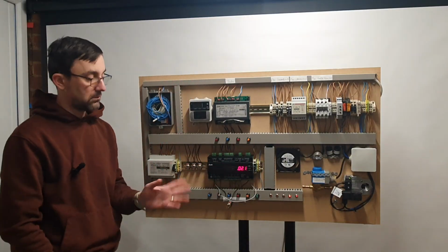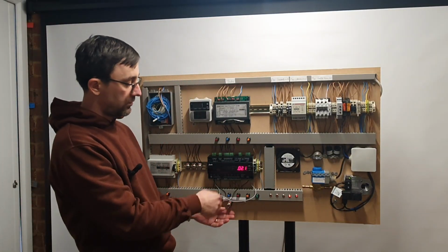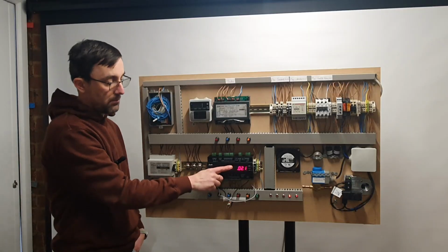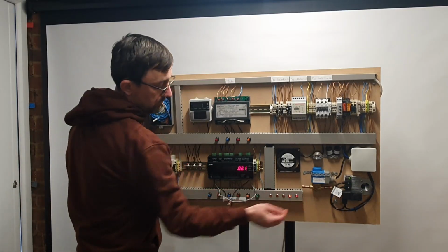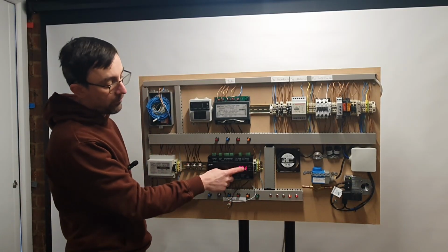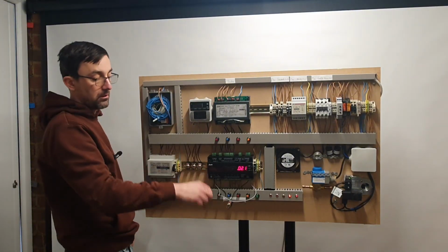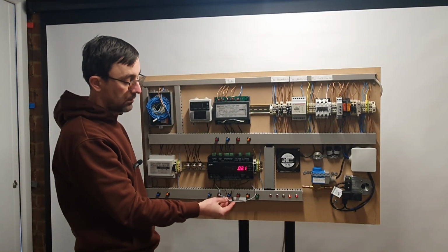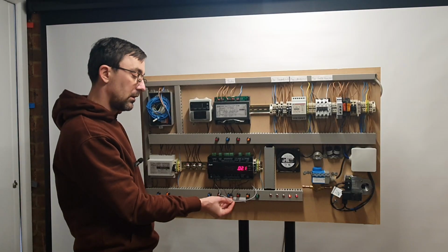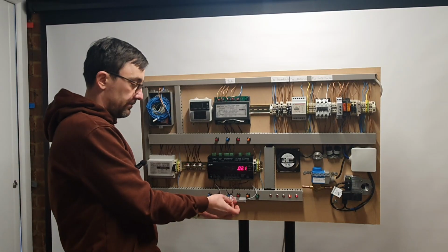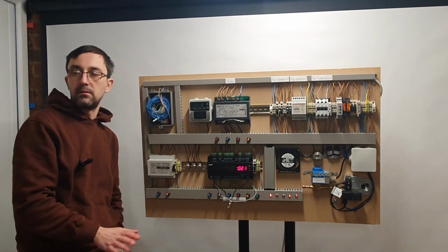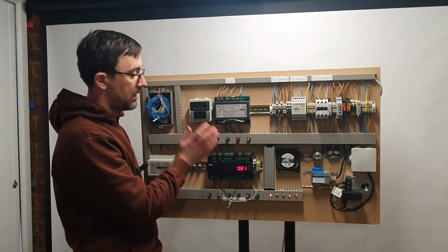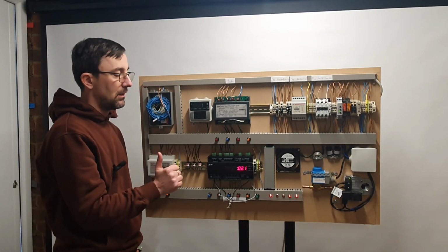It's good. It starts refrigerating. It won't bring on my refrigeration because the set point is 3.5 and my temperature is below the set point, because I'm in thermostat band number 2. If I switch that to a set point of 0 degrees, it starts cooling down. So, okay, we covered this, which is good.